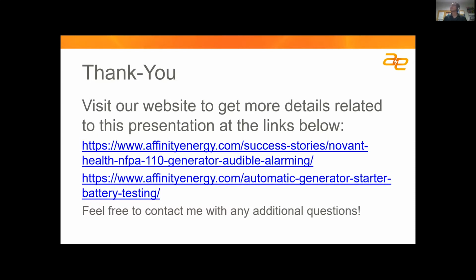The first question is, how easily is VTS interfaced to various generator systems — is it direct connect or via a PLC? Yeah, that's a very good question. So most generator manufacturers currently are providing support for open standards. Modbus, both RTU and TCP, have been the preferred, from what we've seen. I believe there might even be some others offering BACnet, but BACnet through a gateway that they put in their control panel.